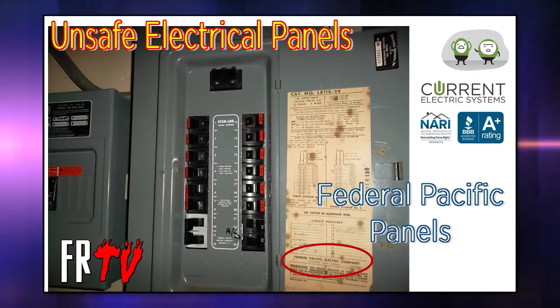The other one that's a big one is called Federal Pacific. You can see them because they have little red handles here, and the position of the breaker is backwards. The problem with the Federal Pacific is that this panel design, the company was fraudulent in their listing, their UL listing when they sent these. So the breakers will not do what they're supposed to do roughly 30% of the time. The worst case scenario, you have an electric dryer and the motor seizes and it starts pulling all kinds of current and that breaker does not trip. This whole thing is going up in flames.